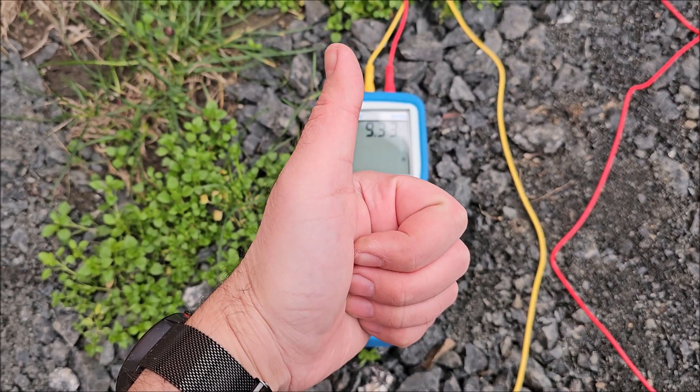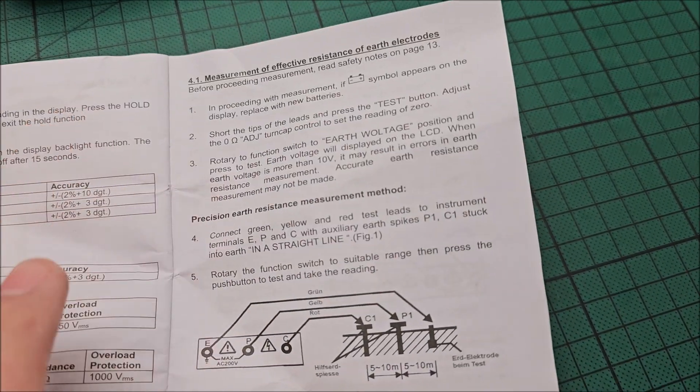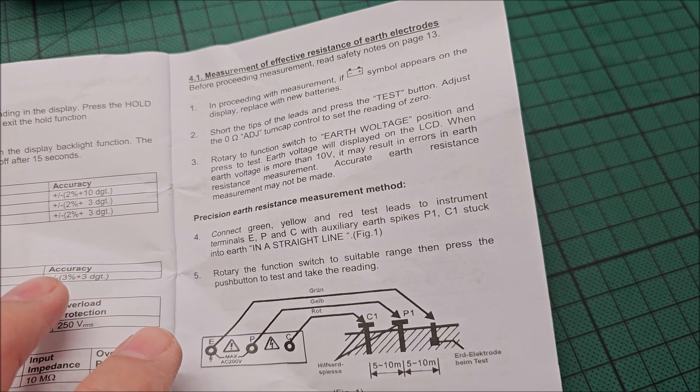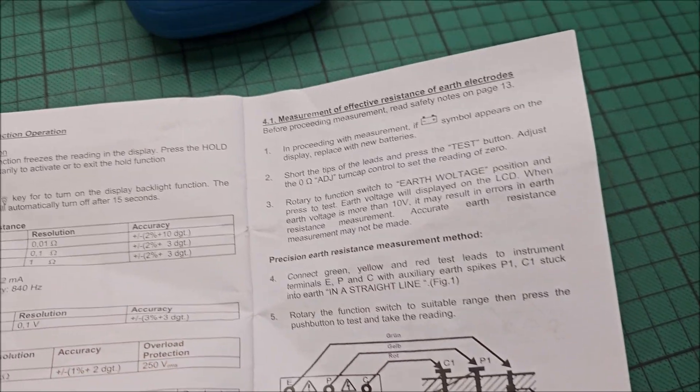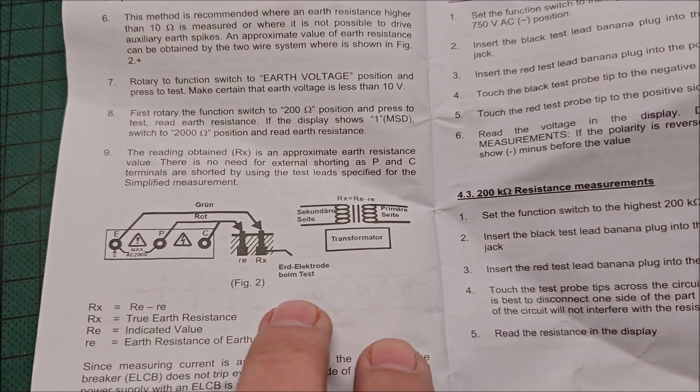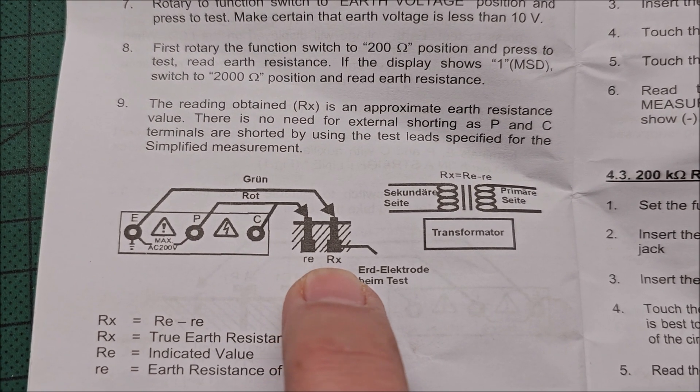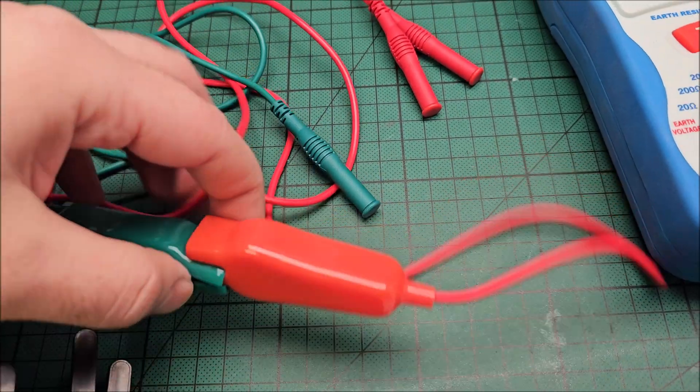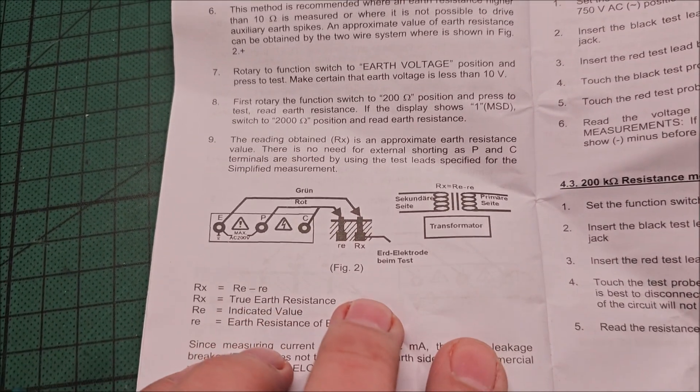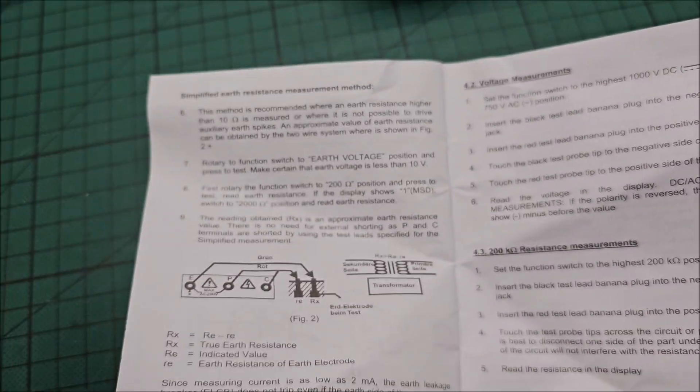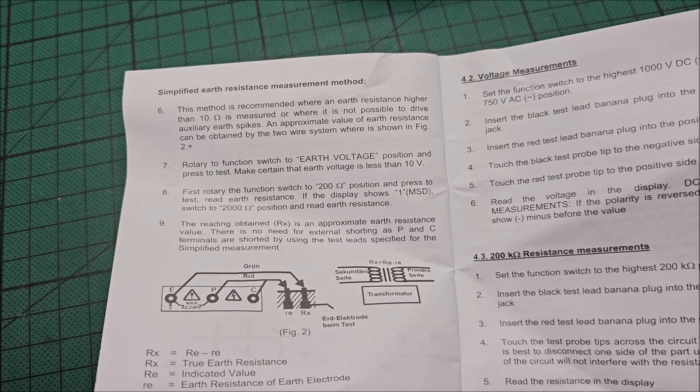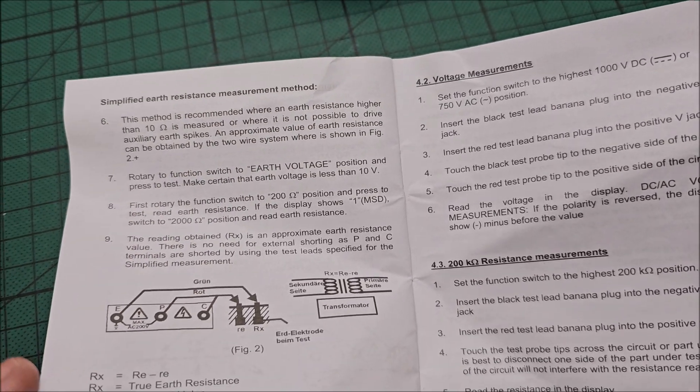Okay, so for us it was perfect and we got a real measurement with this and the measurement is good enough. And if you cannot do this, if you don't have where to put more spikes, you can basically measure in your distribution panel using these clamps and yeah, you are done in that case. But it will not be a definitive value, it's just a simplified measurement with approximate value.